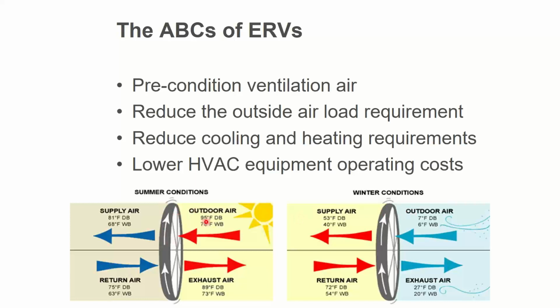In the summertime, the exact opposite thing happens. Now I got some 95-degree air getting sucked into my building for fresh air, and somewhere I have pre-cooled 75-degree exhaust I'm going to throw away. All right, well, now I take that warm energy from the 95 degrees and transfer it into the exhaust air, thereby raising the exhaust air from 75 to 89, and I throw it away. But in return, it cooled my outside air from 95 down to 81. So on a 95-degree day, I'm going to have 81-degree air being brought into my air handler to then be further mixed with the return air, cooled down with my cooling coil, etc.